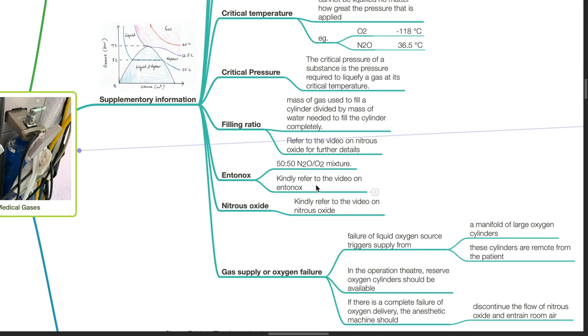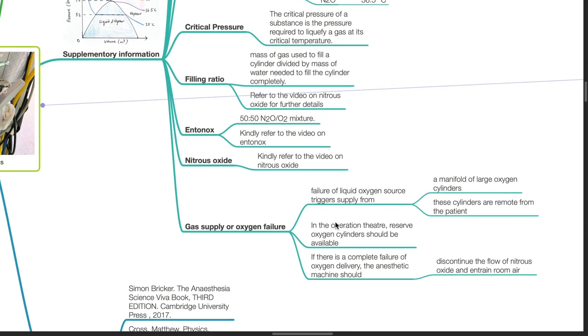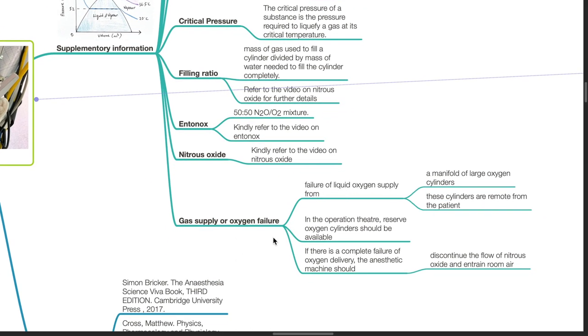Gas supply or oxygen failure can result from failure of liquid oxygen supply from a manifold of large oxygen cylinders remote from the patient. In the operation theatre, reserve oxygen cylinders should be available. If there is a complete failure of oxygen delivery, the anesthetic machine should discontinue the flow of nitrous oxide and entrain room air.